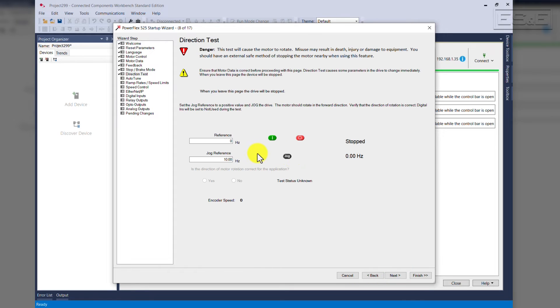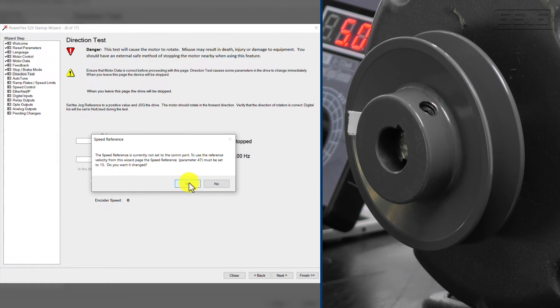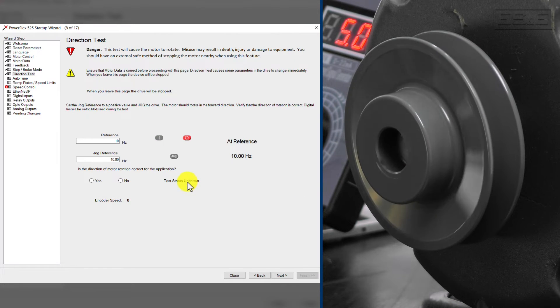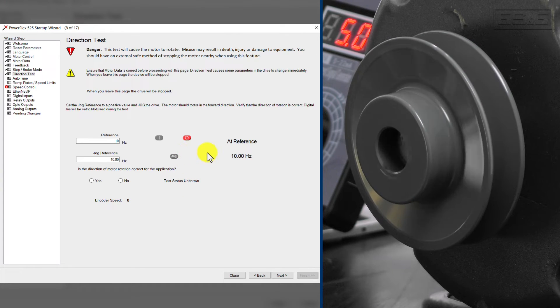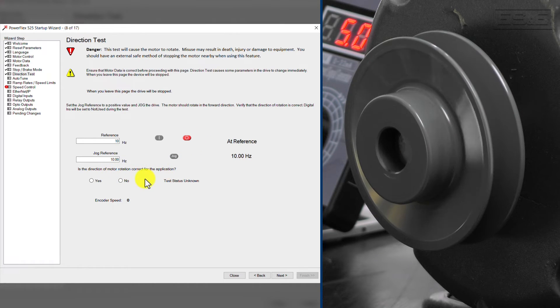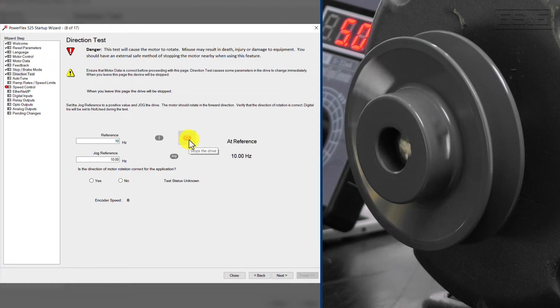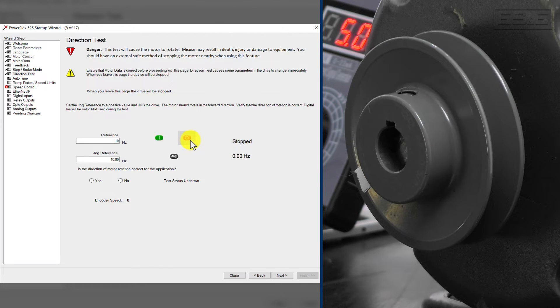This is the point we're going to do the direction test of the motor. I'm going to put in a low frequency of 10 hertz, and I'm going to hit the Start button. Just select Yes to this. As you can see, the motor is starting to turn at 10 hertz.